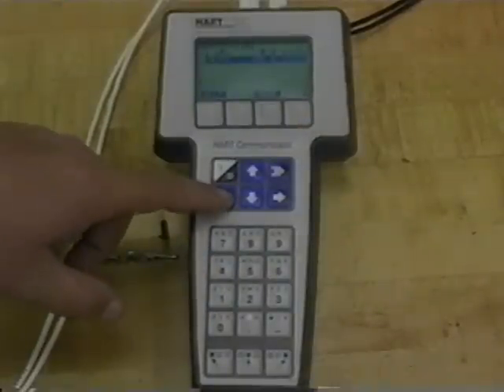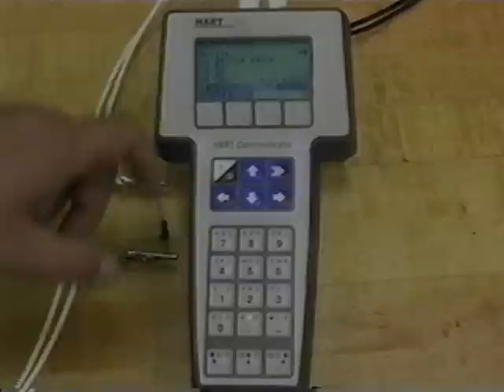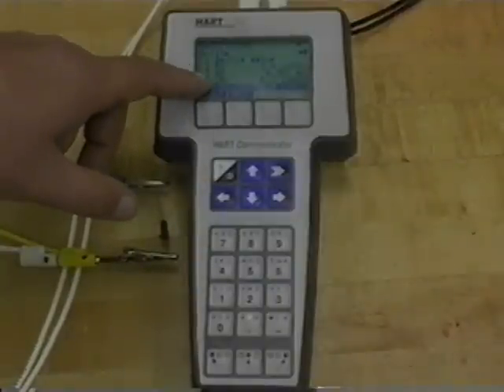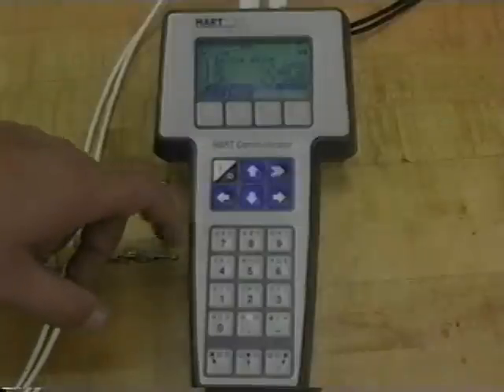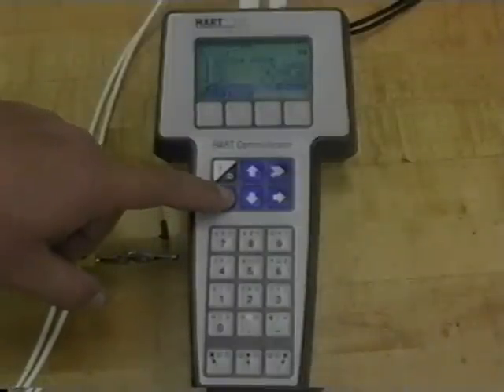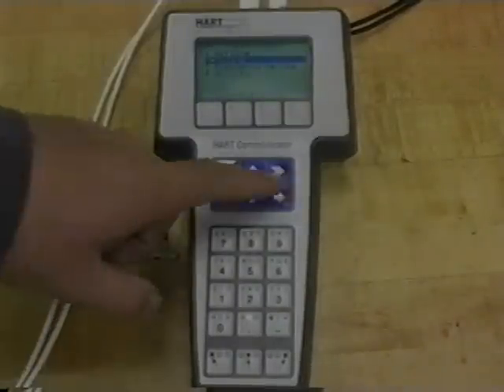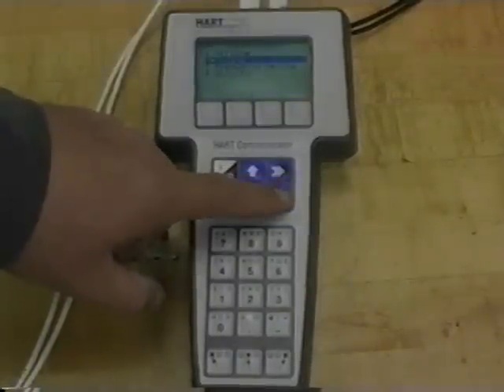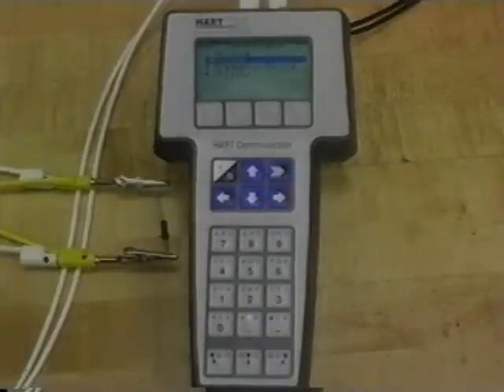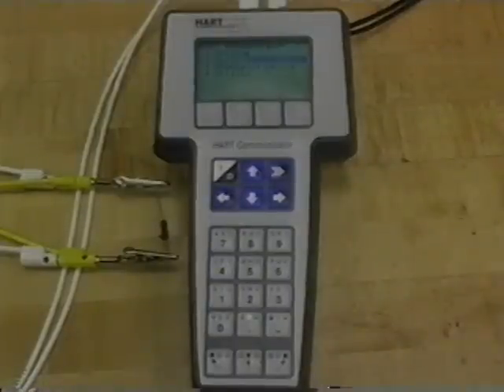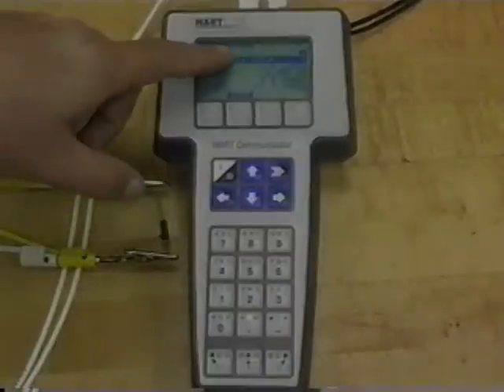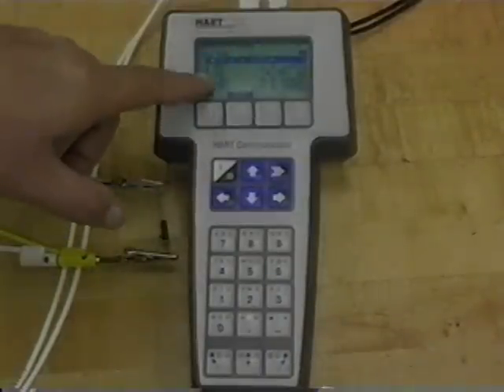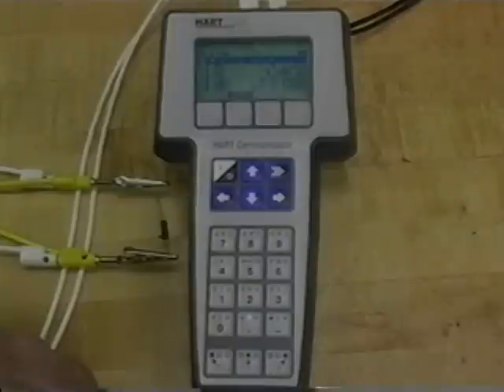If I back out, you can see that the lower range value is 0, the upper range value is 100, and the tag is PT101. If I back out again and then reestablish communication by hitting right on online, we can test our calibration. All the information that we need is in the transmitter. The tag's correct, the lower range and the upper range values are correct.